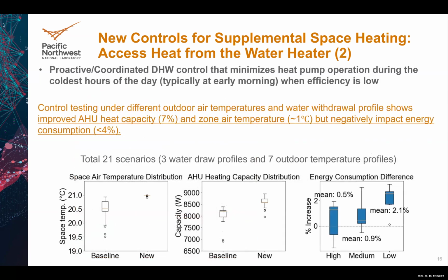So based on this new control, we investigated a total of 21 scenarios. We consider 3 withdrawal profiles and 7 outdoor temperature profiles. Here you can see the 3 water draw profiles. Basically, we consider high water usage, medium water usage, and low water usage. These 3 water usage profiles are from the ASHRAE standards. These 7 outdoor temperature profiles are from Alaska. You know, they have a lot of cold outdoor temperatures during the winter.